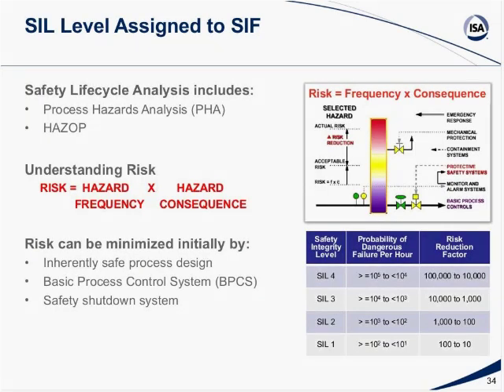Now, when determining whether a SIL 1, SIL 2, or SIL 3 system is needed, the first step always is to conduct a process hazard analysis to determine the functional safety need and identify the tolerable risk level. Now, for the boilers, as Jerry mentioned, most of the time it is SIL 2 as defined by ISA 84. But I'm talking about maybe safety systems which are outside a boiler too, where a hazard analysis is usually the first step. Now, after all of the risk reduction and mitigation impacts from the basic process control system and other layers of protection are taken into account, a user must then compare the residual risk against the risk tolerance. And so if there's still an unacceptably high level of risk, then a risk reduction factor is required.